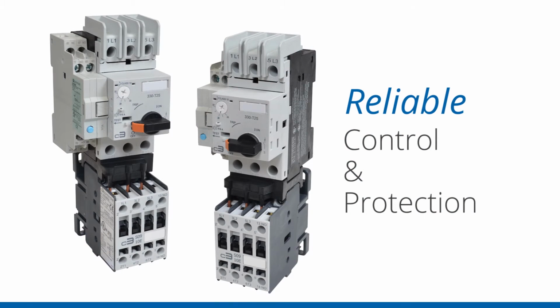Our Type E self-protected combination motor controllers and Type F combination motor controllers can eliminate the need for upstream short circuit protection and provide reliable motor control and protection. We will specifically talk about the applications of these within the National Electric Code and the UL standards requirements to have a UL-listed Type E or Type F combination motor controller, and spend a little time identifying the differences between a Type E self-protected combination motor controller and a Type F combination motor controller.